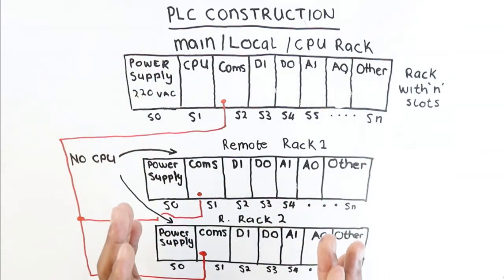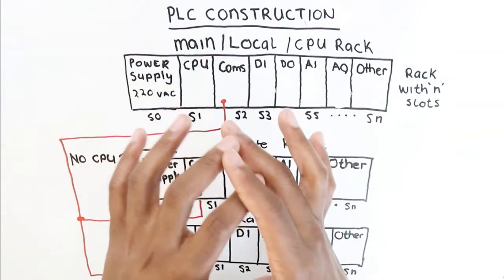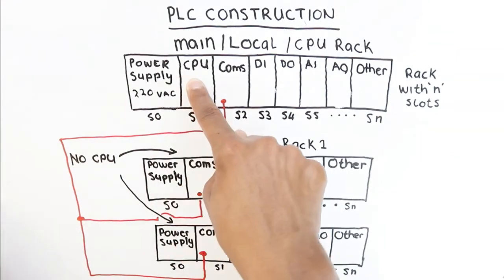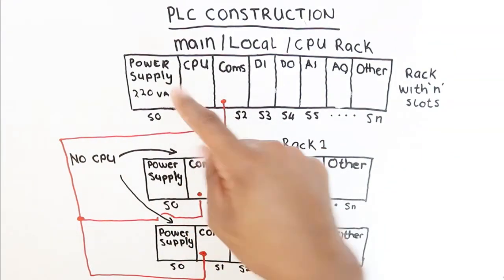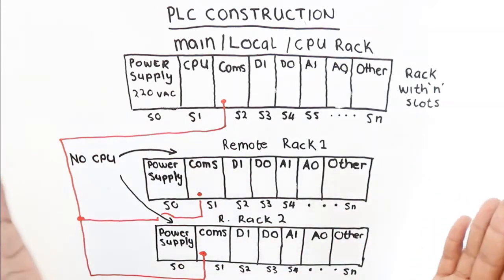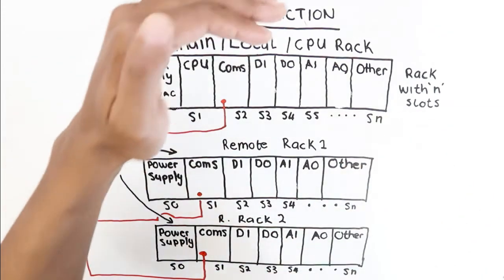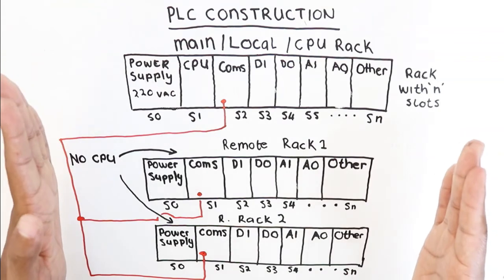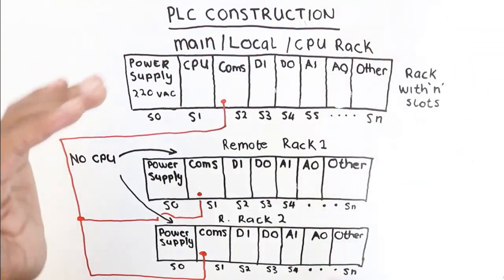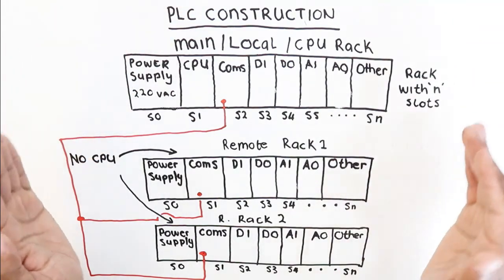There's also a limit: if you have too much I/O being served on that PLC, then it also affects your CPU, your memory of your CPU, and that will then affect your scan time. So what I mean is that the actual hardware or the construction of your PLC is very important because it really affects how you build your program and how you can automate your plant.